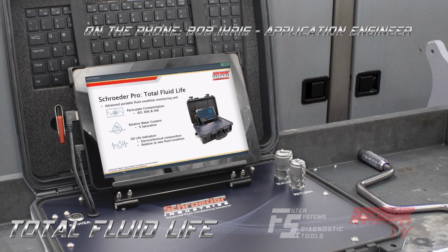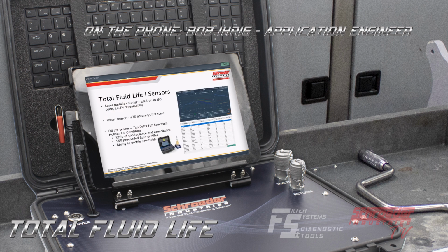And that estimation is based on the electrochemical composition of the fluid relative to a new fluid profile or new fluid condition. So, furthering this discussion on the sensing technology, before we get into that, to the right-hand side, you can see the 10-inch LCD display that's incorporated into this device rather than a small digital display, if you will. You can see our oil life condition, particle analysis, and water content, as well as temperature. But in terms of sensors, nothing crazy: laser particle counter, water sensor, the oil life sensor, also known as a tan delta full spectrum holistic oil condition sensor, which is a mouthful, I apologize, but we'll keep it simple and just call it an oil life sensor.